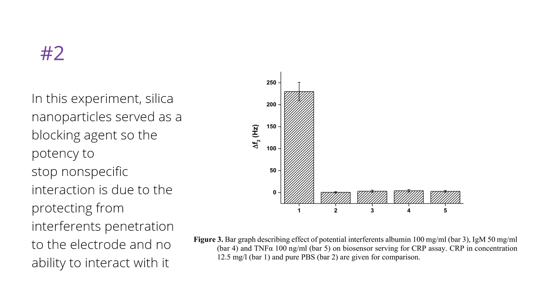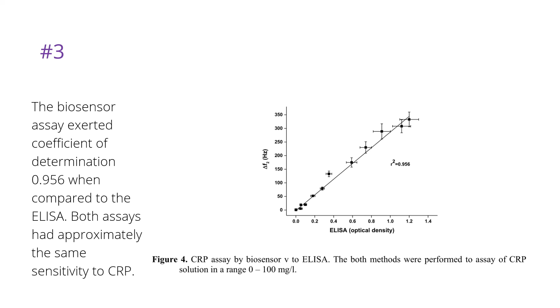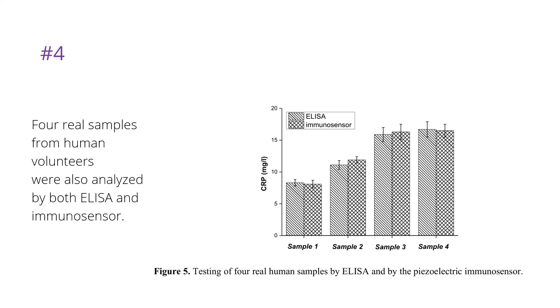Interference testing was performed as another important parameter characterizing an analytical method. The experiment on interference testing can be concluded by a statement that the biosensor is selective for a given analyte. Replacement of the used antibodies by a less selective analog can cause decrease of biosensor selectivity. The samples used for calibration of the biosensor were also measured by standard ELISA, and both assays were mutually correlated. In this study, the results from the immunosensor and ELISA were compared. Looking at the table, it is another confirmation of the immunosensor's plausibility to determine CRP level.